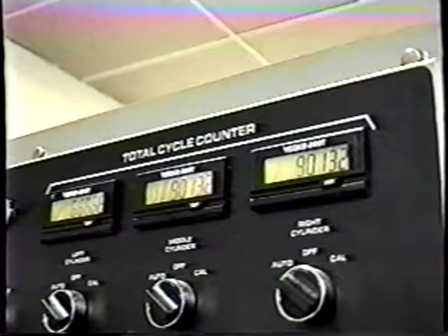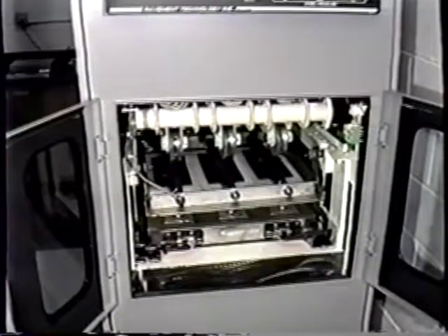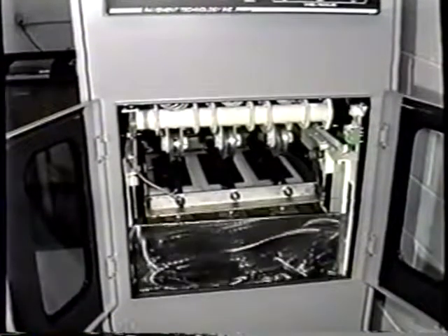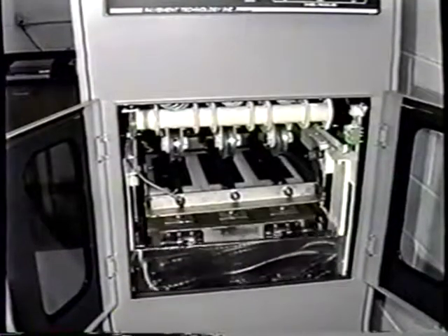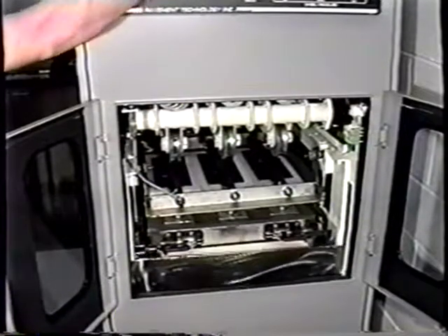On this display, 2 wheels have stopped and only one remains running in a fatigue cracking test. A stainless steel tank, pump, and reservoir are provided to test specimens underwater for moisture susceptibility. The tank raises into position, fills with water, and the entire cycle is run underwater. Water is then drained and the tank is lowered. Each step is easily handled from the control panel.